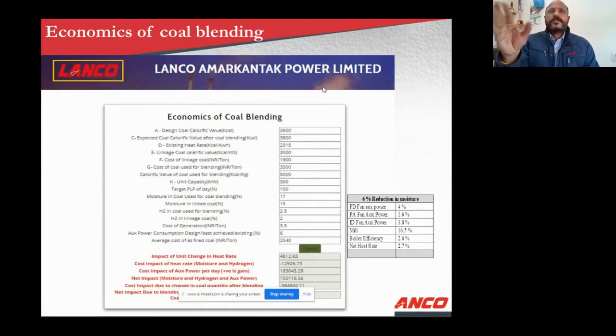Then hydrogen in linkage coal. Then cost of generation. Then with that we have calculated the impact on the heat rate as well as the auxiliary power if the various blending regimes are considered. So this is very easy, if thought is given, a relationship can be easily established with the available empirical formulas or curves given by the OEM, and they are brought together.